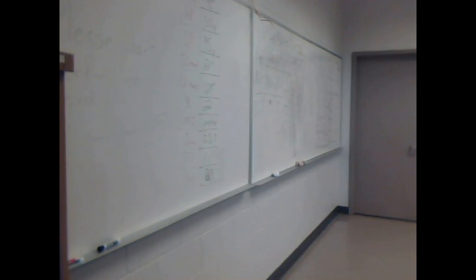Go back to your list of low suction. Is it listed there? Is improper load on the evaporator, 25-6, listed as a cause for low suction? Okay, so at the beginning on the improper load, I would write LS for low suction. This can cause low suction. Y'all follow me? In the section 25-6, right where it begins, it can cause low suction. Now, can it cause high suction? Go to your high suction list and see if 25-6 is listed. Yeah. All right, I'm going to put a comma, and now I'm going to write HS. It can cause high suction. That way I don't have to look back and forth every time.